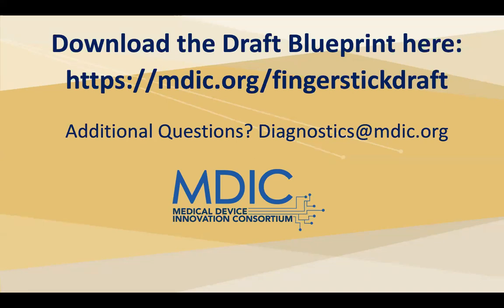Okay. Another comment, and this might be a discussion between the different panelists. You usually do not use the thumb or little finger, so you'd need to use only the 6 fingers. Thoughts? Comments? Yes, that is a standard practice. The thumb or the little finger is not used, and none of our requirements actually goes more than 5 tests, so you still have 1 spare to use.